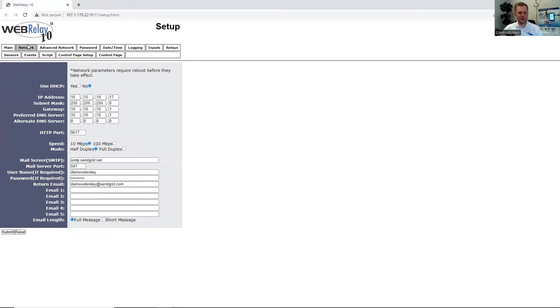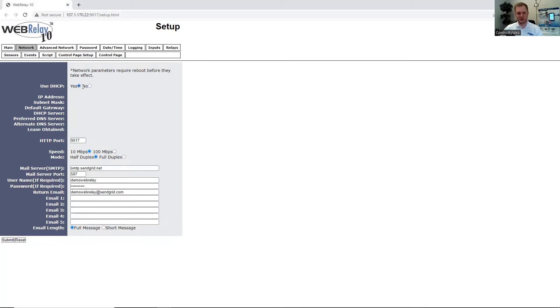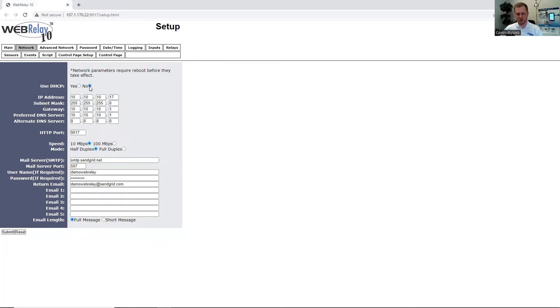Under the Networks tab, since the WebRelay 10 Plus supports DHCP, we can enable that — the router will assign the network settings for the unit, and you would need to access your local network's router for that information. For the purposes of this webinar, we're going to have it disabled. You can enter an IP address local to the network and also specify the port numbers. We also have speed and mode here, which we recommend leaving at 10 megabits to preserve power and increase the life of the unit. Mode establishes how the information is communicated over ethernet. We have additional details in our user's manual about this.